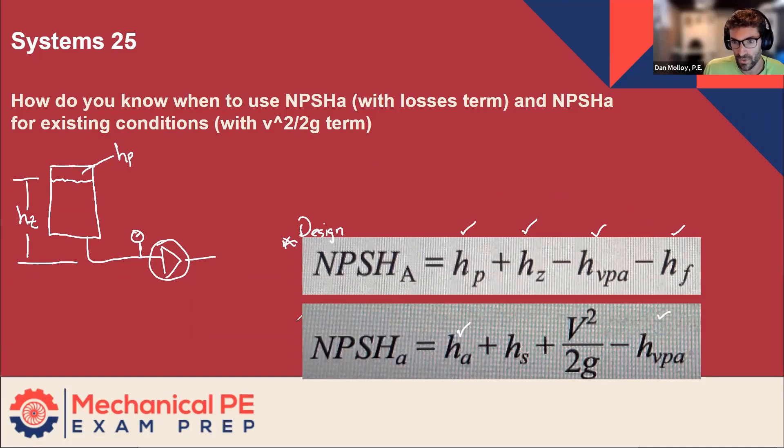So what changes that would have you use the other equation? This is the existing conditions equation. The answer is: it's already built. So instead of telling you all this other information about what's happening way upstream on the source, on the suction side, we don't care about that because we have a real measurement at the gauge at the inlet of the pump. So we can disregard everything upstream, which is why the losses term doesn't appear and the hz term doesn't appear. Because it doesn't matter if there is a height of a water column sitting on the left side - the impact of that is measured by this gauge.